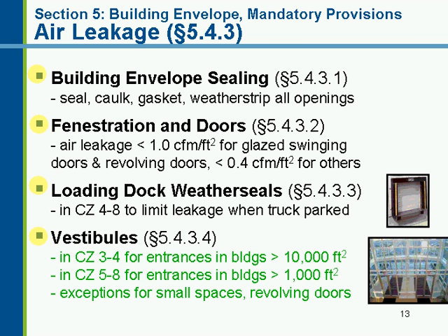Section 5.4.3.4 contains requirements for vestibules, and this is where there have been some changes. The intent, a lot has to do with clarification, but there's also some slight increase in stringency. So within that section, vestibules, it requires that building entrances that separate conditioned space from the exterior shall be protected with an enclosed vestibule. Now, a couple of key terms there. One is the term building entrance, and there's a definition in Chapter 2 of building entrance. That says any doorway, set of doors, turnstile, vestibule, or other form of portal ordinarily used to gain access to the building by its users and occupants. So the key thing there is that we're talking about an entrance that's ordinarily used to gain occupancy.